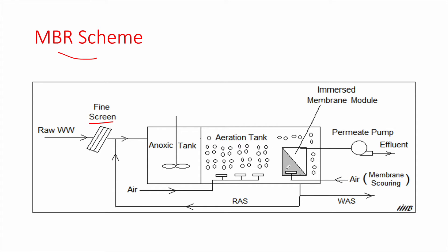Within the aeration tank we have immersed membrane modules — the MBR membranes — where we have the massive reduction of organic matter, BOD and COD. This is also where ammonia is transformed into nitrates through nitrification. Some sludge, called returned activated sludge, is then pumped back into the anoxic tank to remove the nitrate through denitrification, transforming it into nitrogen gas.